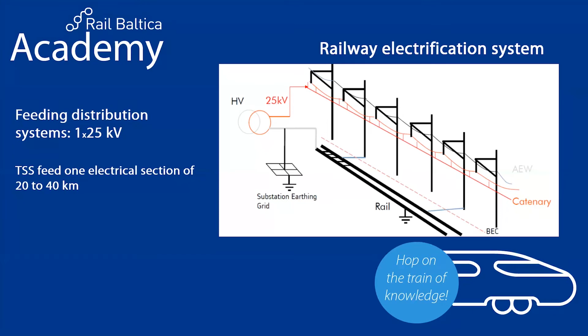If we zoom out a little, we can see this 1x25 system with 3 substations, each feeding 20 to 40 kilometers. In these drawings we have 2 transformers, not working at the same time, but this is for redundancy reasons - it's a backup transformer for the substation. We have 3 electrical sections, so above the train you can see 3 sections of catenary, with 1 separation section between each. The reason for these separation sections is that we use different pairs of phases in the substations.